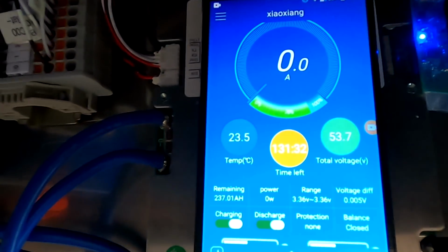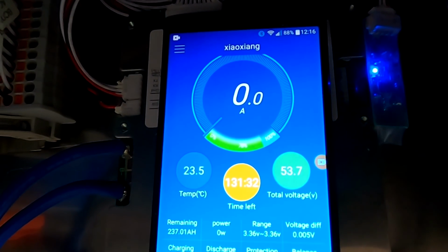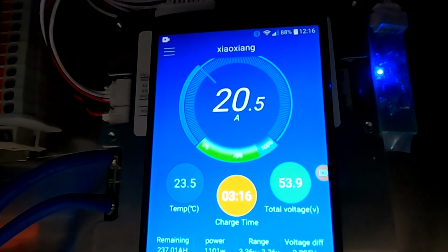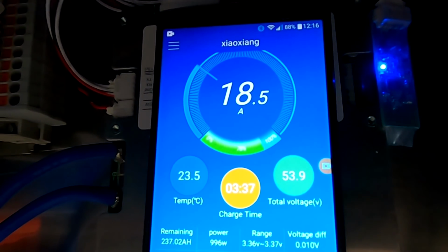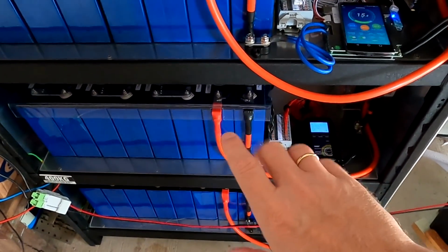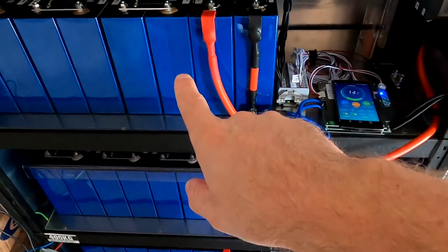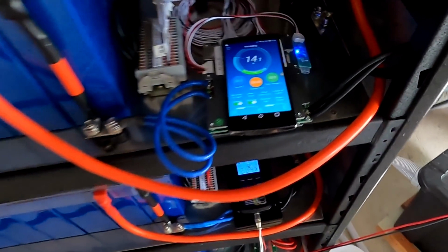Okay, I'm turning on the circuit breaker again and we can see a high inrush current into this battery, hopefully. Maybe not - 20 amps only. So the battery banks are now equalizing, transferring energy from these 2 battery banks into this one because this was off for a few minutes. But as you can see, it's not too high.